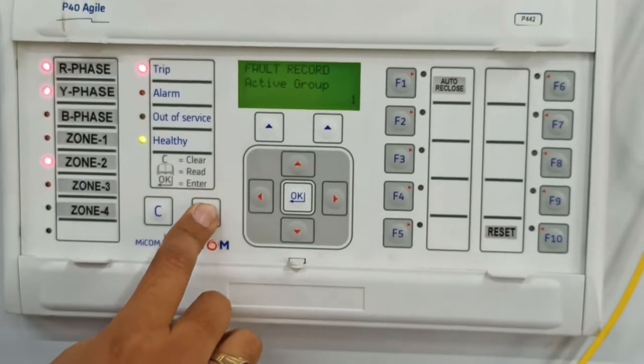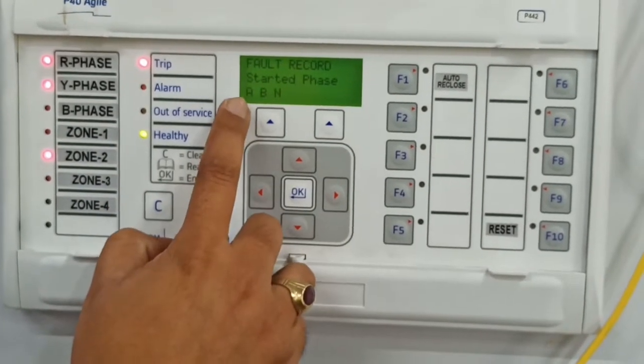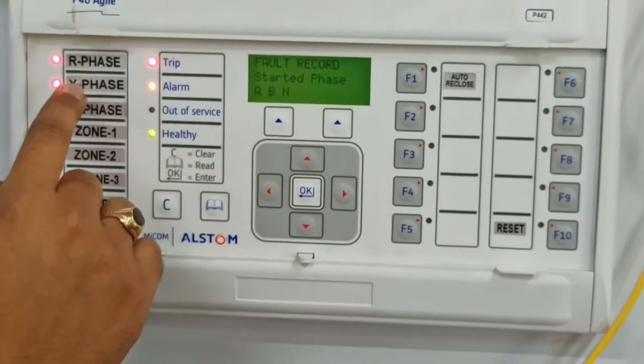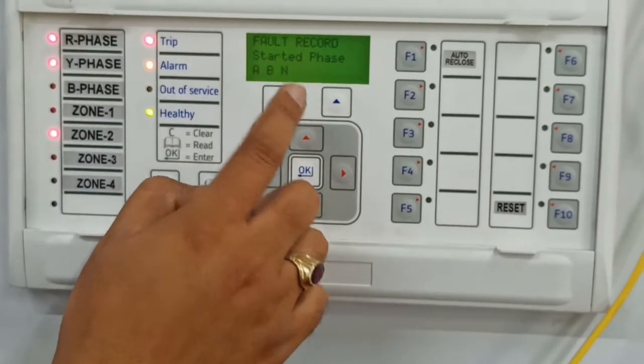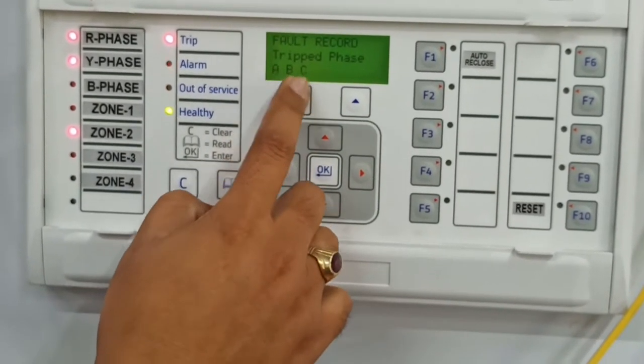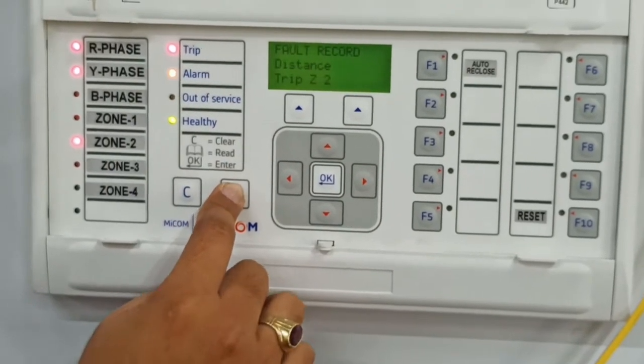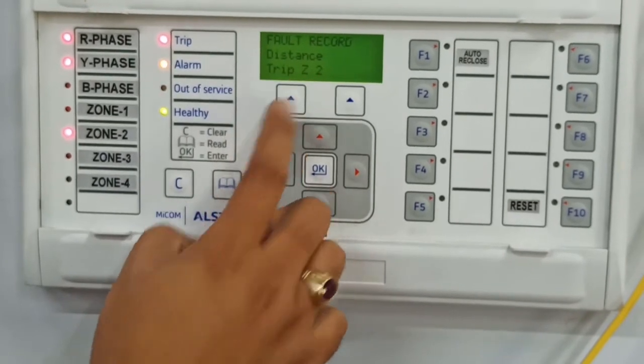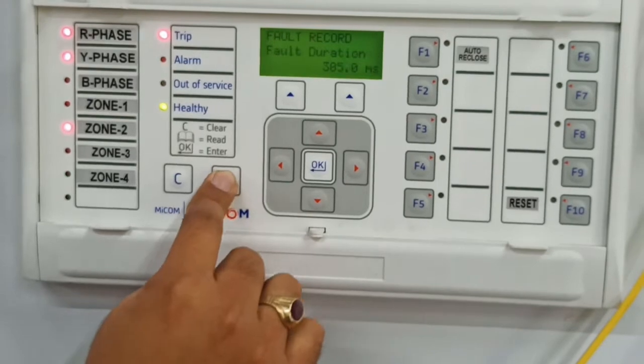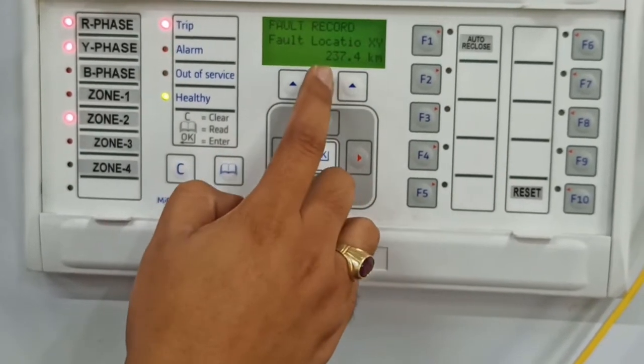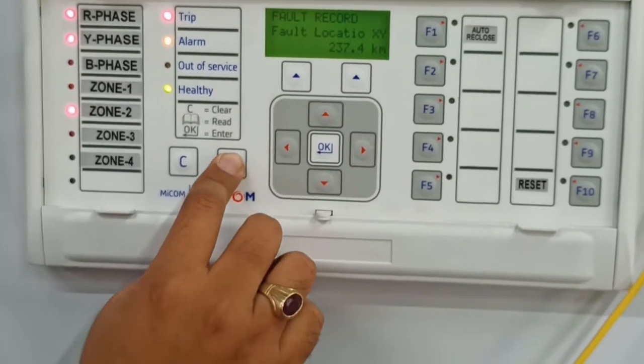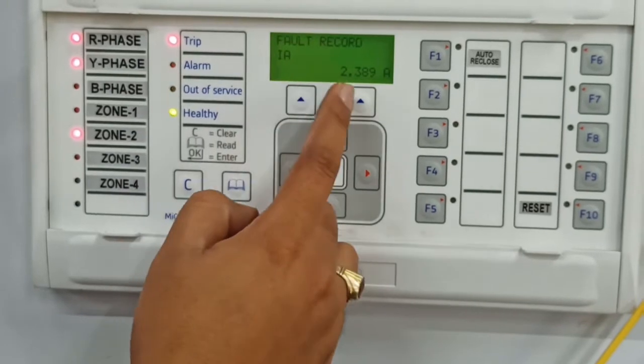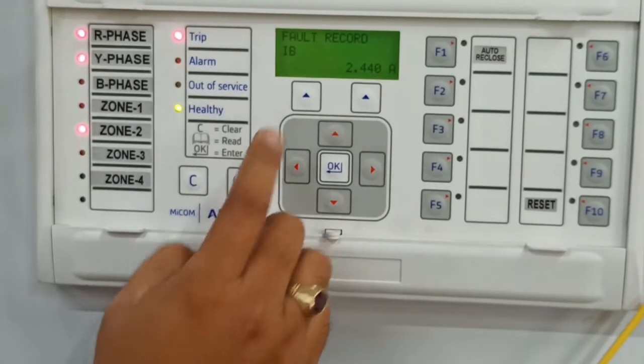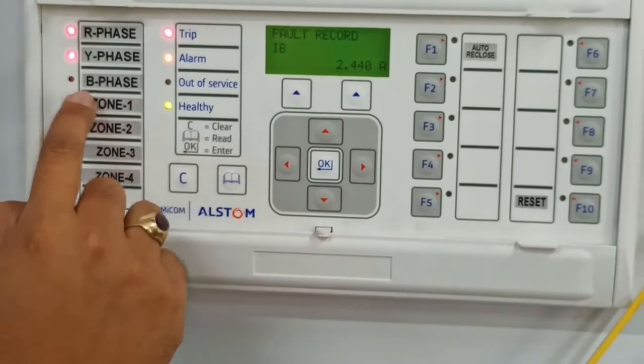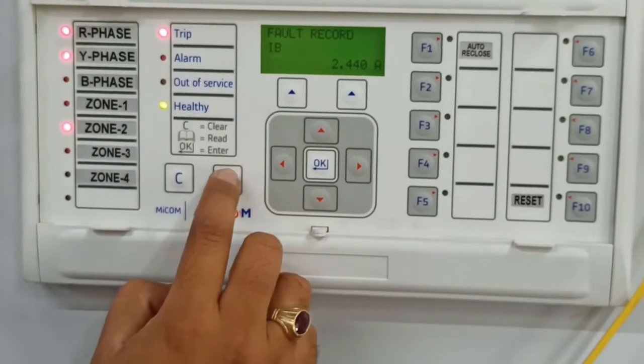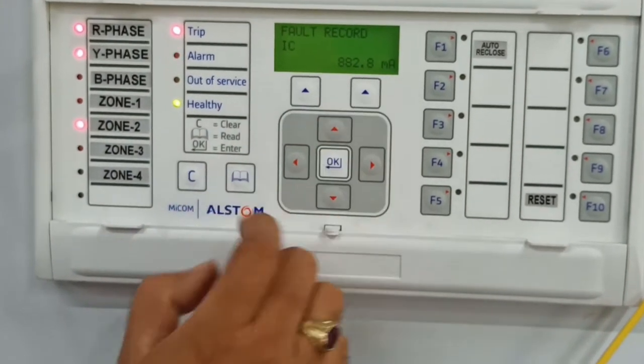Now let's see the reading of the fault. Active fault group is 1. The fault started in A, B and neutral. So RY phase is AB here, and the neutral fault is here. Then ABC is trip, and the distance trip is in zone 2. Fault location is at 237.4 kilometer. Current IA is high, 2.38 ampere, and IB is 2.44 ampere. At C phase there is no fault, that's why the current is low, 892.8 milliampere.